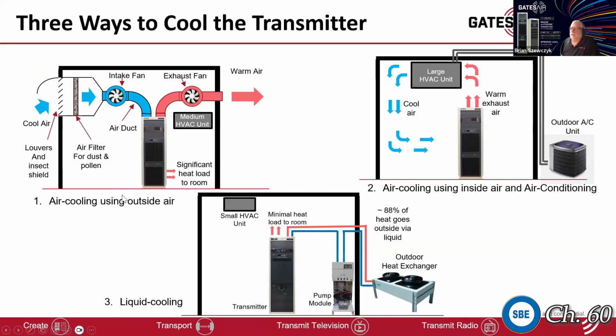I visited a few years back during repack a mountaintop site that basically had one of our TV transmitters in it, and the site was air conditioned, but at some point someone put an economizer in, which basically took outside air and blew it in. So when we walked into this building, the RF plumbing had the same patina on it as the RF plumbing going up the tower, because of the humidity and moisture that was in the environment, because it was very high mountain. It was in the clouds a lot. So when the economizer was in, it was just literally taking all that moisture and blowing it into the building.